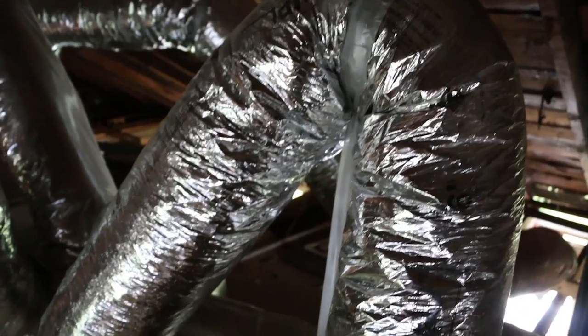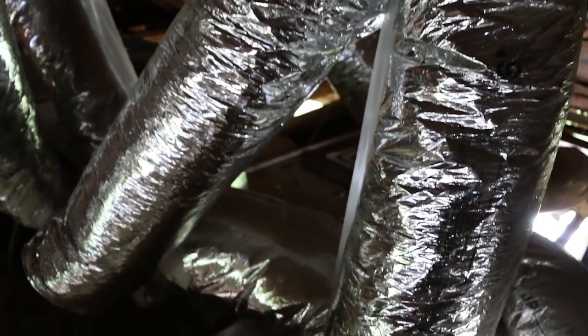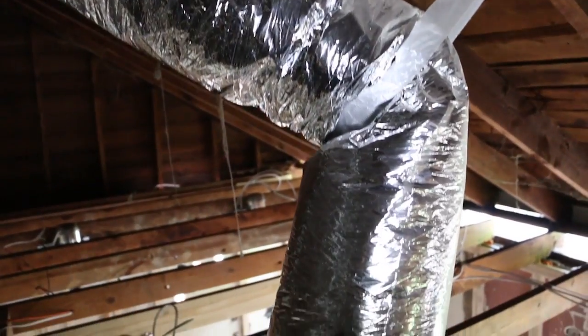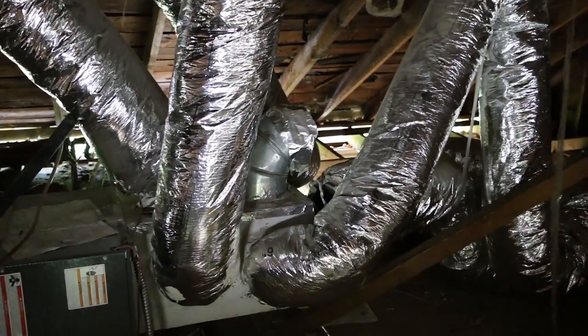So they took a relatively efficient air source heat pump and installed ductwork horribly. The ductwork has crimps, it has bends, and you can see that behind me now.